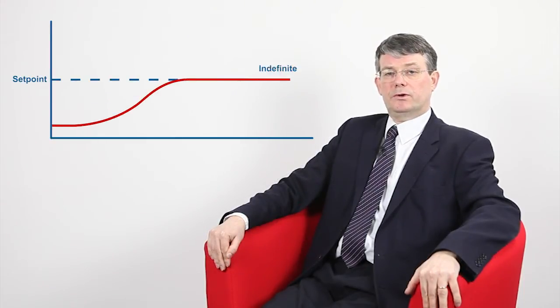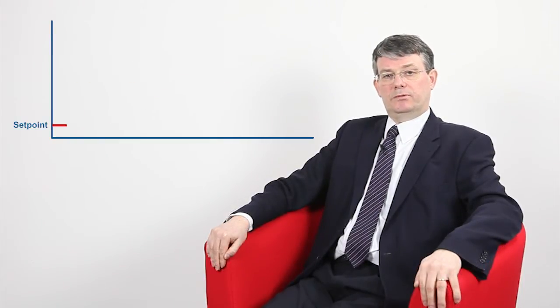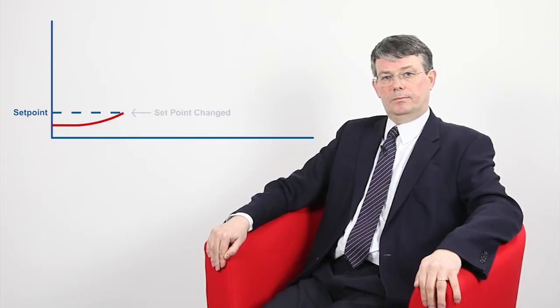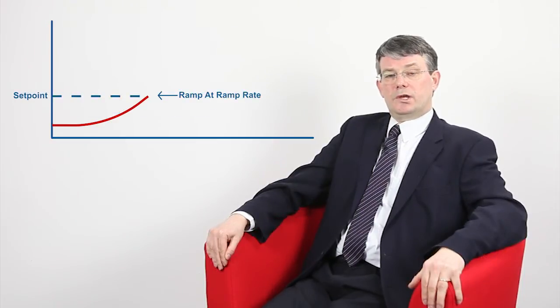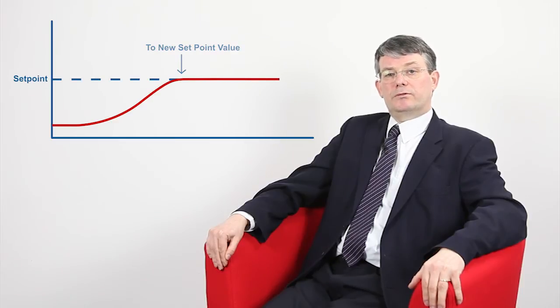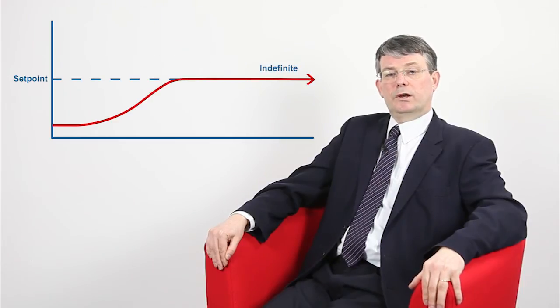With set point ramping, the effective set point value is moved slowly towards its final target value. The controller keeps the process in line with this effective set point value, thus protecting the process from harm. The user enters the set point ramp rate, and this is the value at which the effective set point is moved towards its final value.